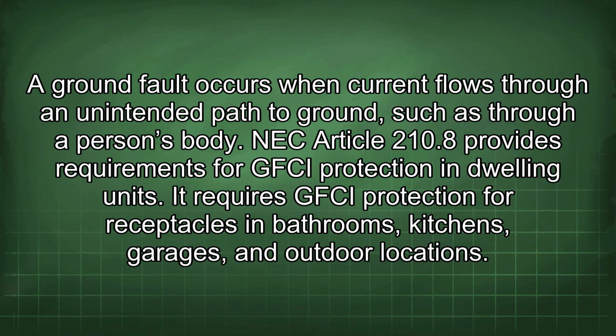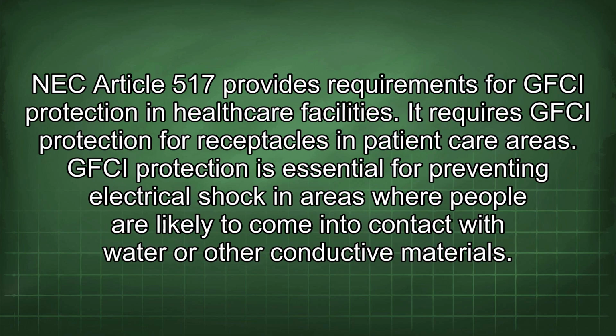NEC Article 210.8 provides requirements for GFCI protection in dwelling units. It requires GFCI protection for receptacles in bathrooms, kitchens, garages, and outdoor locations. NEC Article 517 provides requirements for GFCI protection in healthcare facilities. It requires GFCI protection for receptacles in patient care areas.